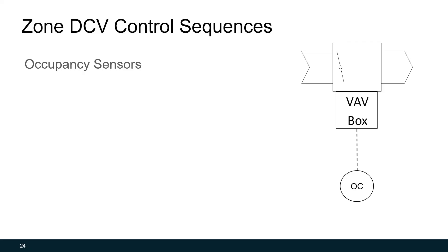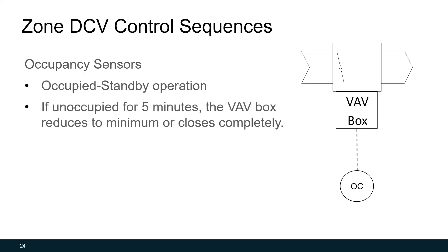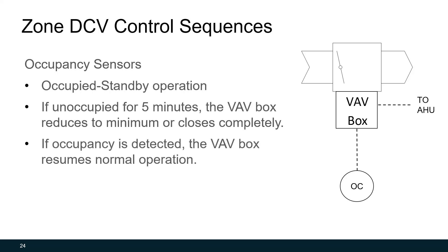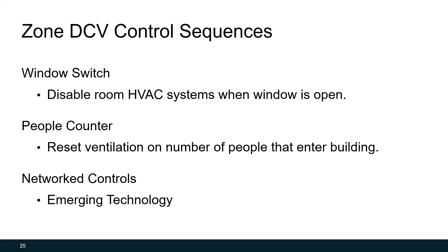It's a bit simpler with binary occupancy sensors. We can use something called occupied standby operation. This is typical for, say, an office — if the office is unoccupied for five or ten minutes, the VAV box can either reduce to minimum airflow or close completely so you're not putting any air into the space. If occupancy is then detected, the VAV box can resume normal operation. We can also use window switches to disable HVAC systems when the window is open, people counters to reset the airflow rate at the air handling unit based on the number of people entering the building, or emerging network controls technology to accurately determine occupancy using Wi-Fi networks.